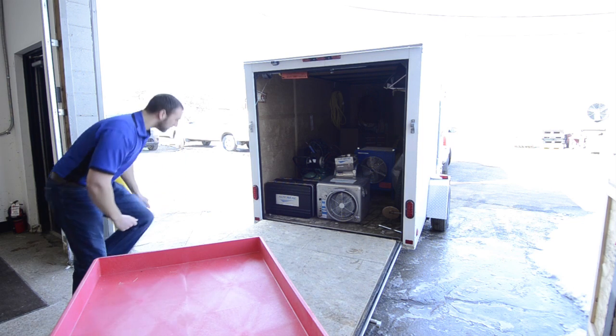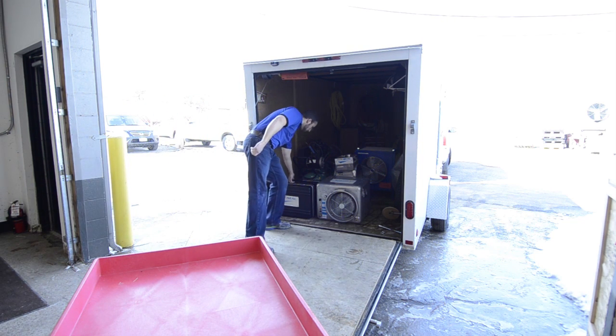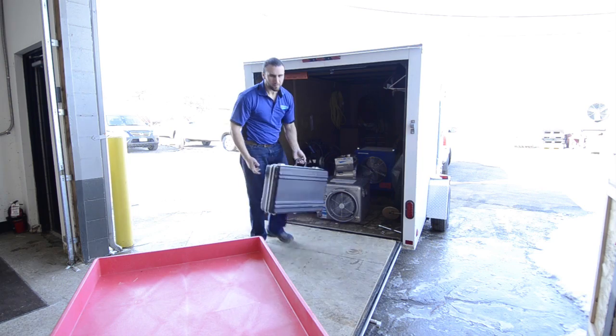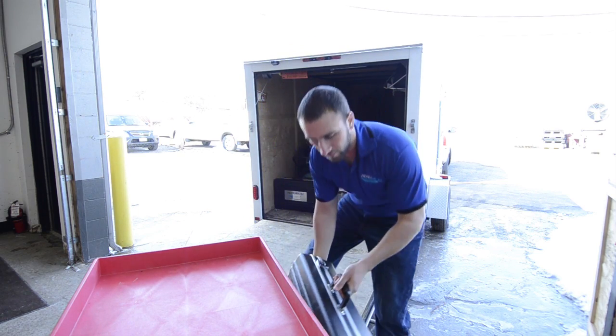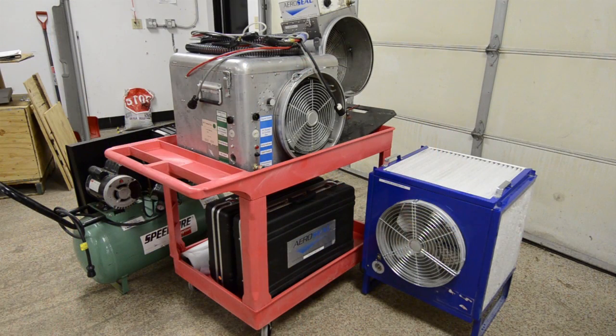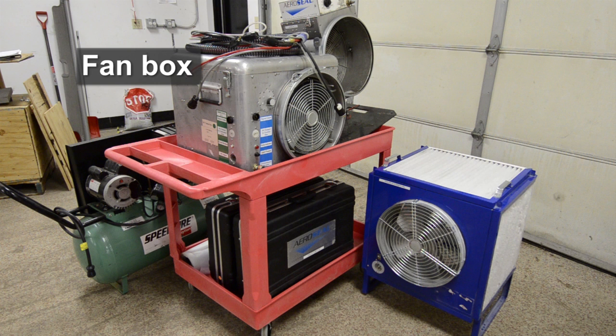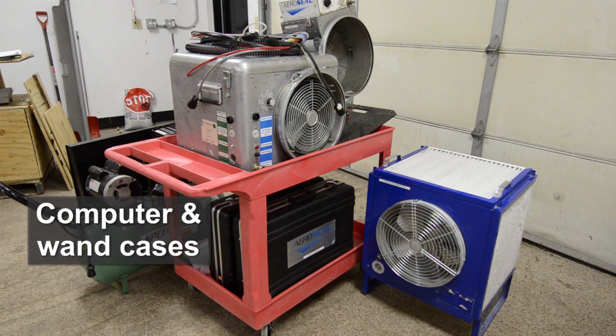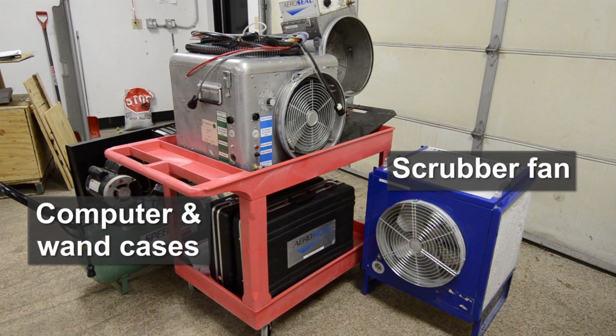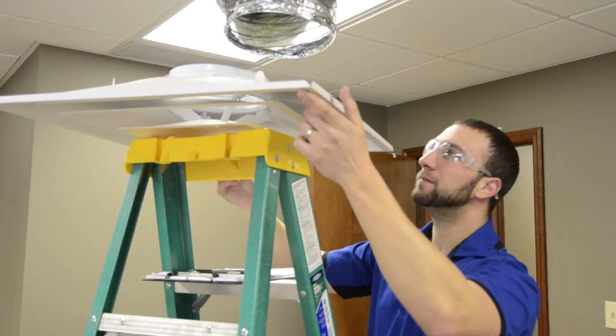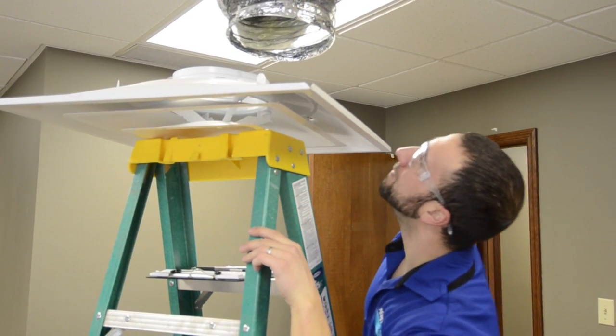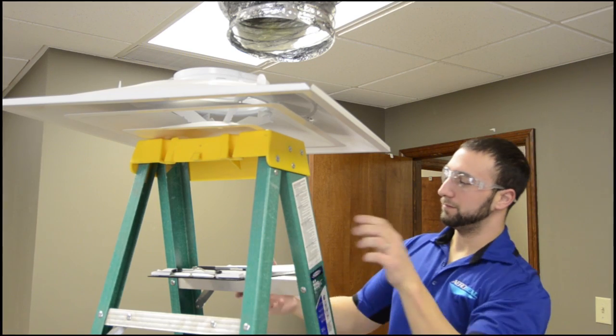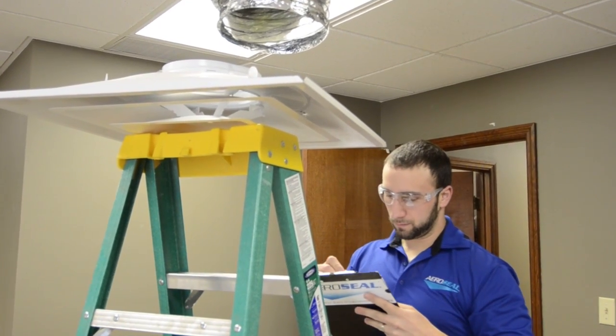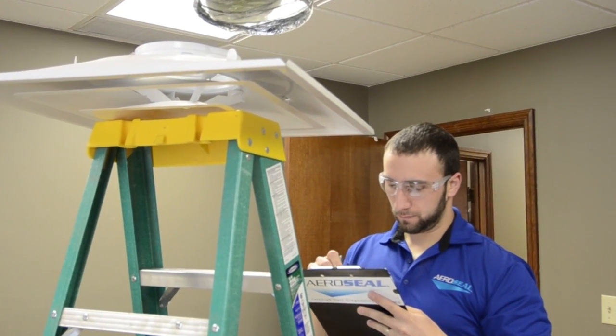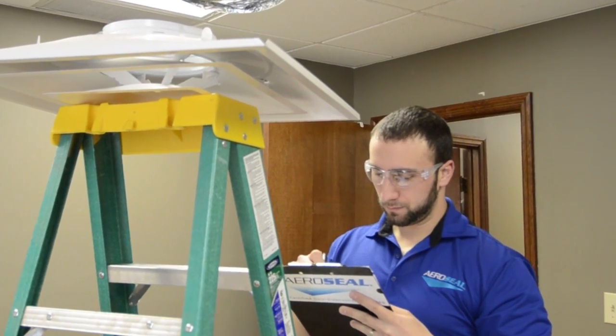Most Aeroseal commercial jobs start with our equipment being unloaded near the building's mechanical room, on a rooftop, or at a previously determined injection site. The major components of Aeroseal equipment include the fan box, compressor, computer and wand cases, and a scrubber fan. Before any seal process begins, a thorough review of the space is conducted, starting with an inspection of the ductwork. During the initial walkthrough, the locations for injection will be determined.